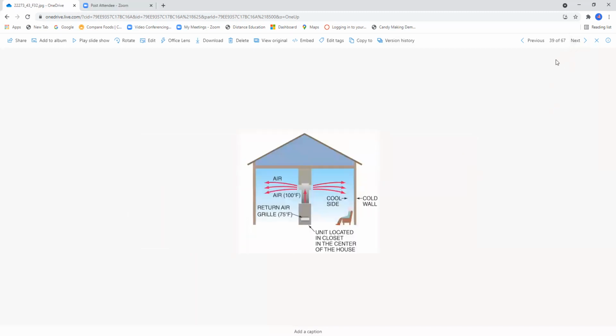Okay, we talked about this earlier in the previous PowerPoint presentation. Airflow is extremely critical on a heat pump. If the ducting is not done correctly, you're going to have the cold side effect. You will have areas that will be too hot, areas that are too cold. Heating, this is a critical issue. So pay attention to the ducting design when you're installing a heat pump, whether it be a split system or a package unit.